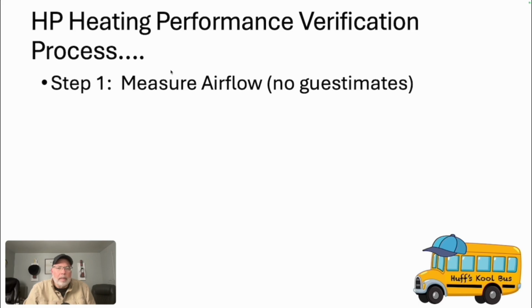Our BTUs per hour, the formula for that is 1.08 multiplied by the cubic feet per minute of airflow multiplied by the delta T. Now, again, we're measuring the heat pump operating without the help of any aux heat. So we're just running the heat pump right now, and we're measuring what the heat pump itself is doing to find out either why the system's running a lot, or whether it's running correctly, right? And so to be able to do that, we have to measure airflow first. Can't be any guesstimates, can't be anything like that.